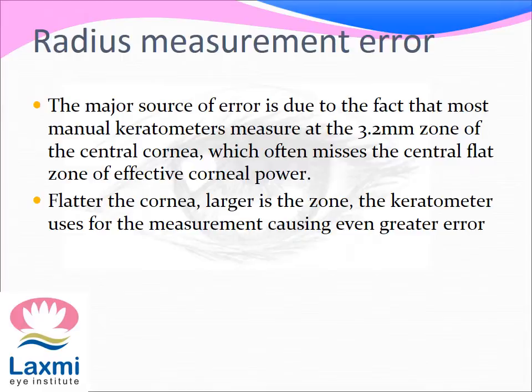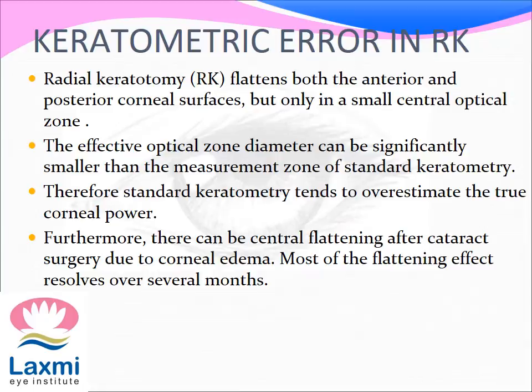The error in measuring the radius of curvature is a major source of error. Most manual keratometers measure at the 3.2 mm zone of the central cornea, which often misses the central flat zone of effective corneal power. However, the flatter the cornea, the larger the zone the keratometer uses for measurement, causing an even greater error.